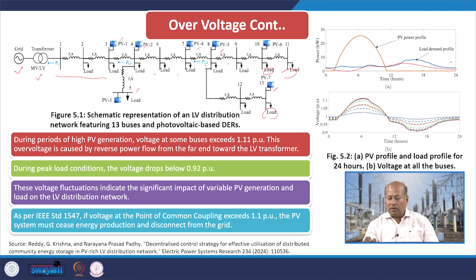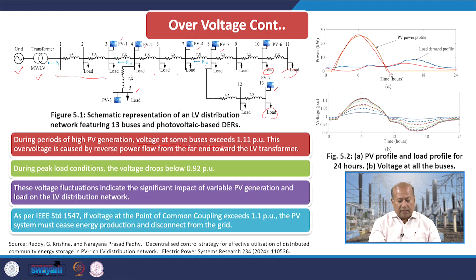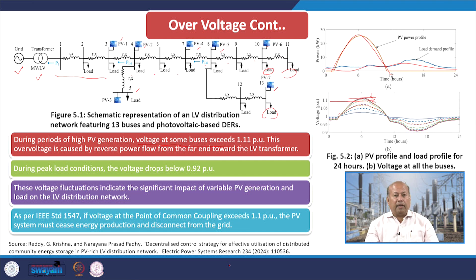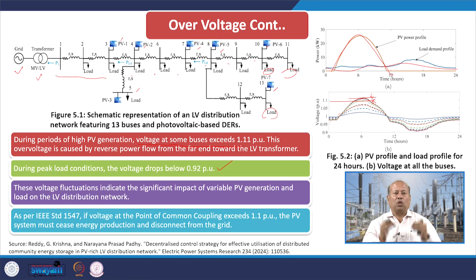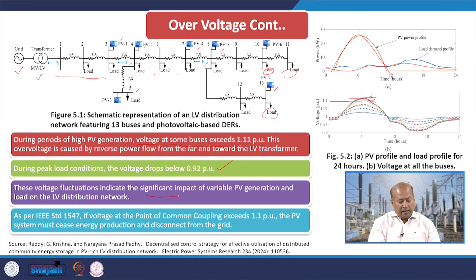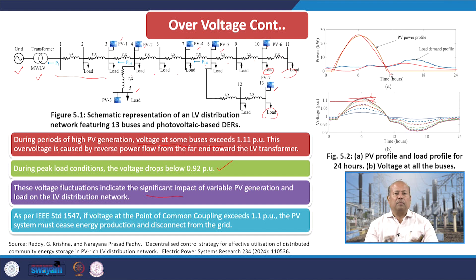The classic load profiles and PV generation profiles are shown, and voltage at each and every bus can easily be calculated. But during the period of high PV generation, voltage at some buses exceeds 1.1 per unit — meaning those buses experience more voltage due to excess PV penetration. And during peak load conditions the voltage drops below 0.92 per unit. This voltage fluctuation indicates the significant impact of variable PV generation and load on the low voltage distribution network.